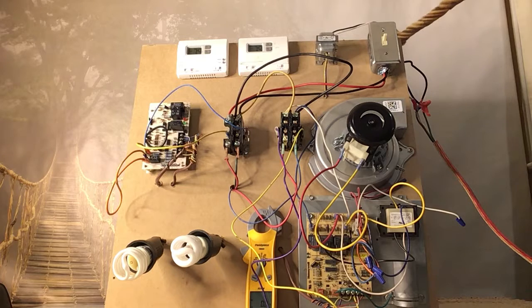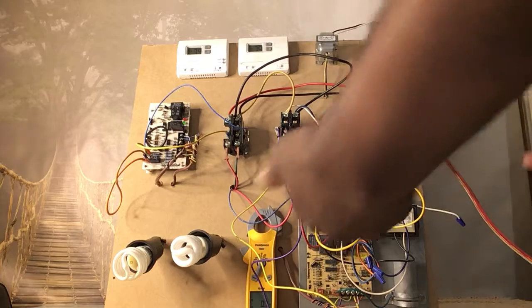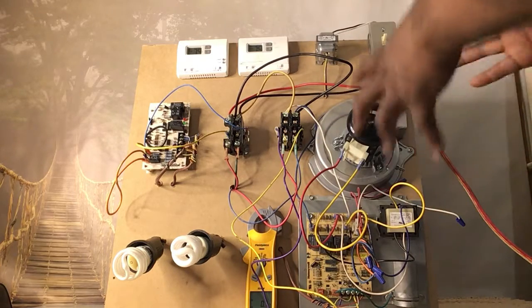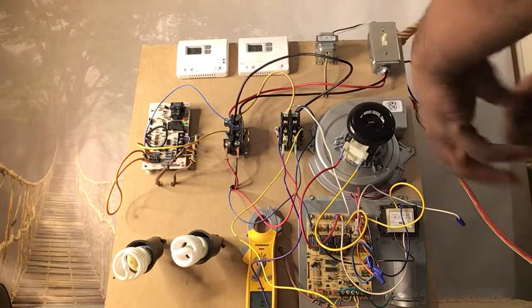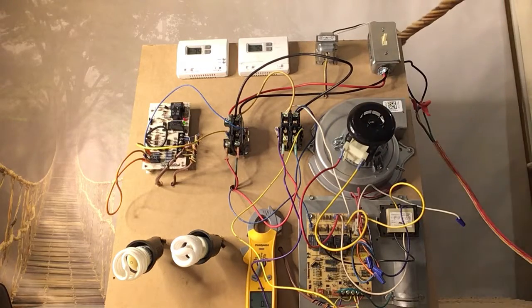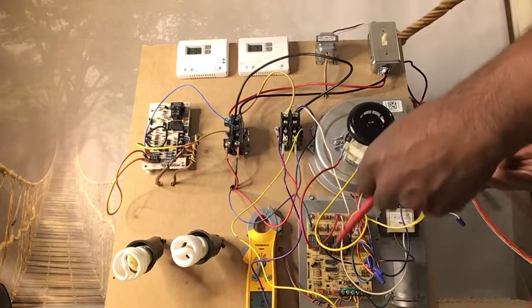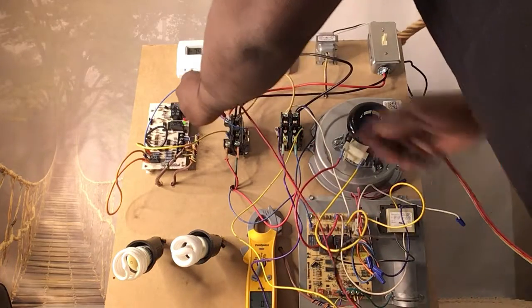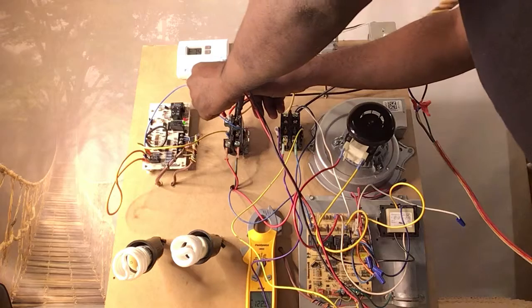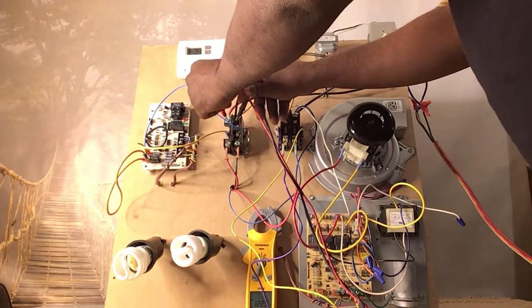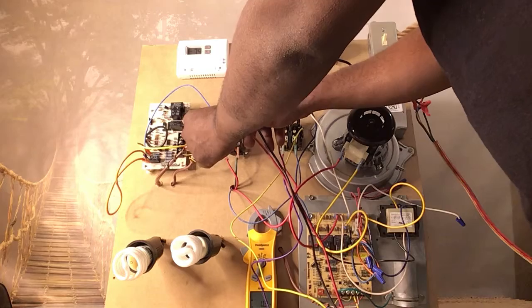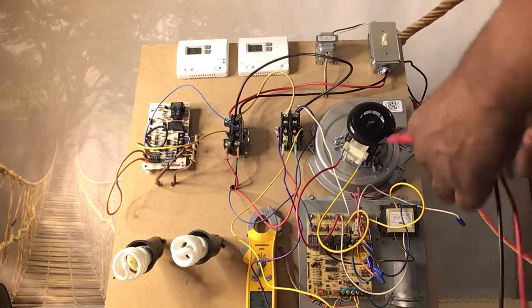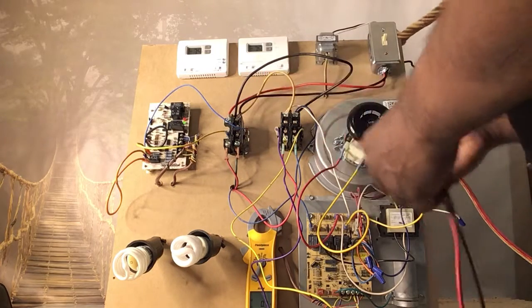Boom. So we're off. Basically, this video is strictly for showing you some simple troubleshooting techniques, or how to utilize your voltmeter in terms of checking power. So you will still have 120 volts here, but now that the system is shut down, you will have no 120 volts here because you haven't activated anything yet. You haven't asked the system to do anything. So there's no 24 volts being applied to this contact coil in order to close it.